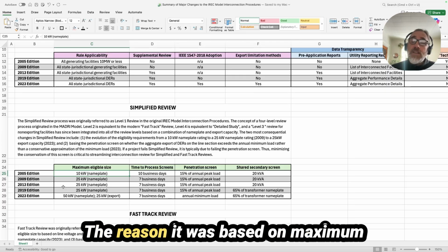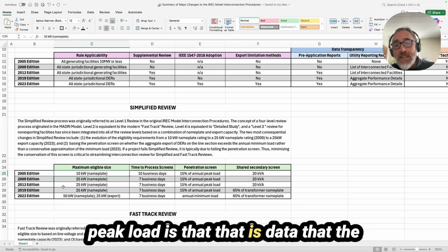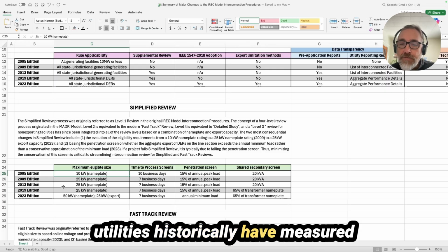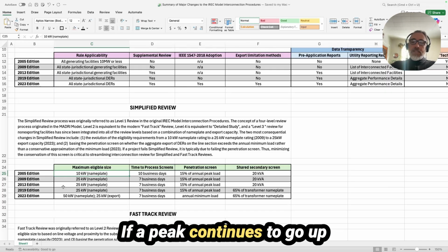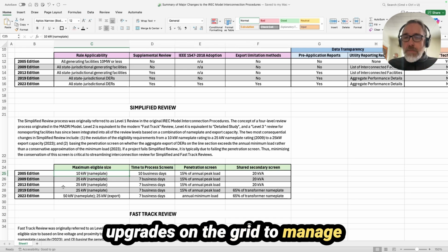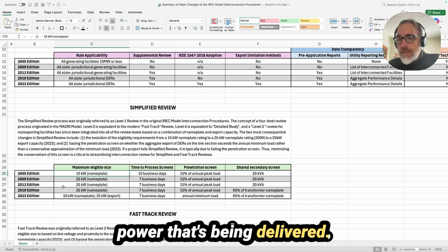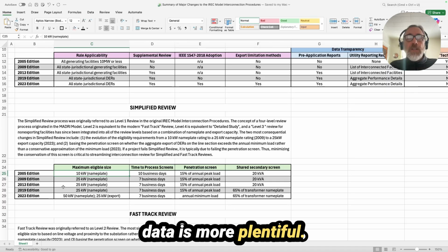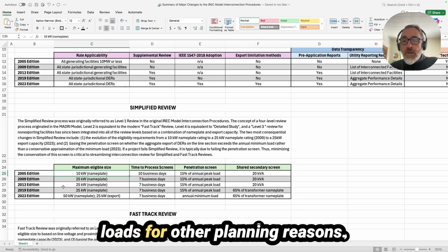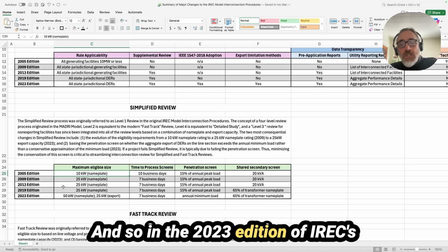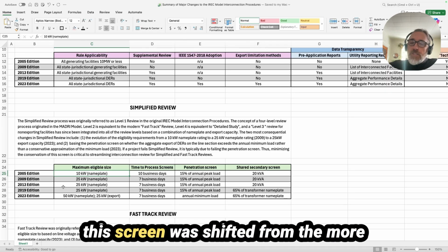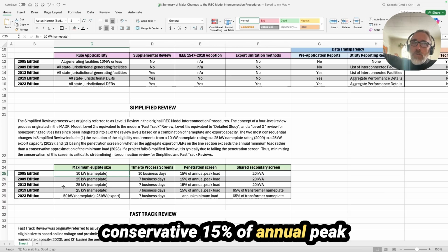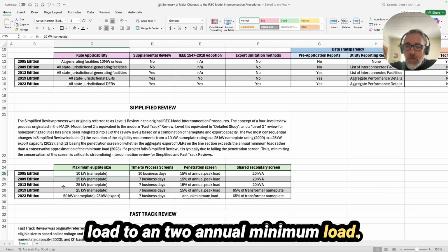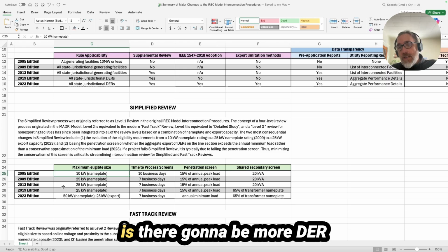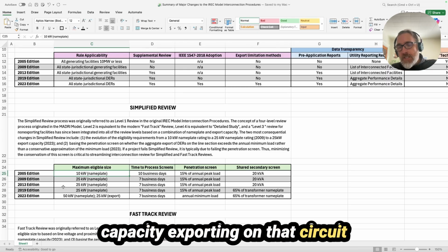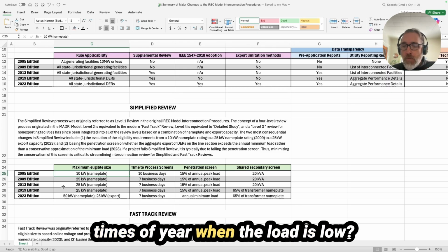The reason it was based on maximum peak load is that that is data that the utilities historically have measured for the purposes of planning. If a peak continues to go up and up, they may need to make upgrades on the grid to manage the increasing magnitude of power that's being delivered. These days, as we know, data is more plentiful and utilities measure minimum loads for other planning reasons. And so in the 2023 edition of IREC Model Interconnection Procedures, this screen was shifted from the more conservative 15% of annual peak load to annual minimum load. And this more precisely evaluates, is there going to be more DER capacity exporting on that circuit than there is load during those times of year when the load is low?